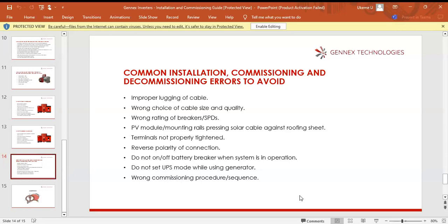Do not set UPS mode while using a generator. UPS mode on the inverter will narrow down the range of operation of the inverter. It could be 220 to 230 volts or something like that. So when the input drops a little below that value, the inverter will be switching up and down, trying to maintain a balance. But if you choose the appliance mode, that gives you a wide input range, like from 170 to about 275 or so. That will give you a wide operating range, and then there won't be any disturbance.